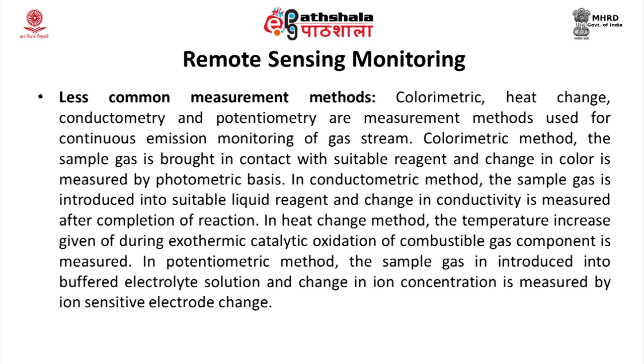Less commonly used measurement methods for flue gases include: the colorimetric method (sample gas is brought into contact with a suitable reagent and any change in color is measured on a photometric basis); the conductometric method (sample gas is introduced into a suitable liquid reagent and change in conductivity is measured); the heat change method (temperature increase during exothermic catalytic oxidation of combustible gas components is measured); and the potentiometric method (sample gas is introduced into a buffered electrolyte solution and change in ionic concentration is measured by an ion-sensitive electrode).